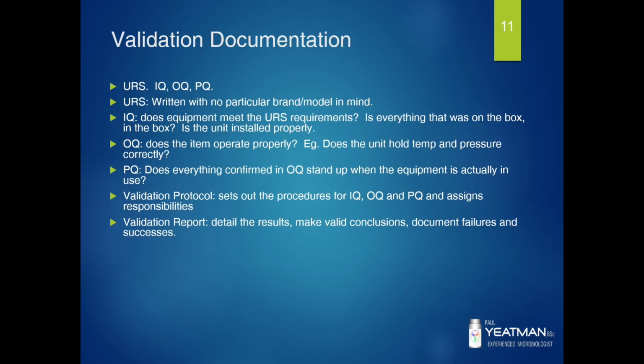is the unit installed properly. Once the unit is installed, then we follow the OQ, which determines whether or not the item operates properly. For example, does the unit hold temperature and pressure correctly? And then once we've completed that work, we go into the PQ or performance qualification, which confirms everything in the OQ stands up when the equipment is actually in use.